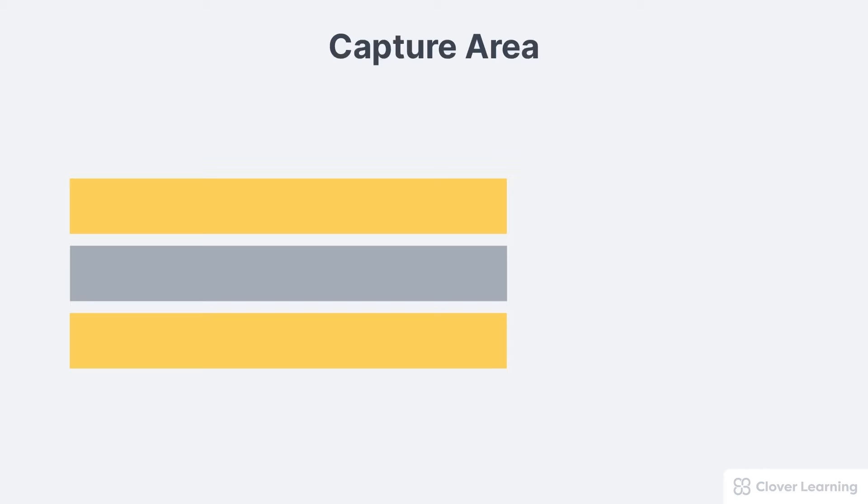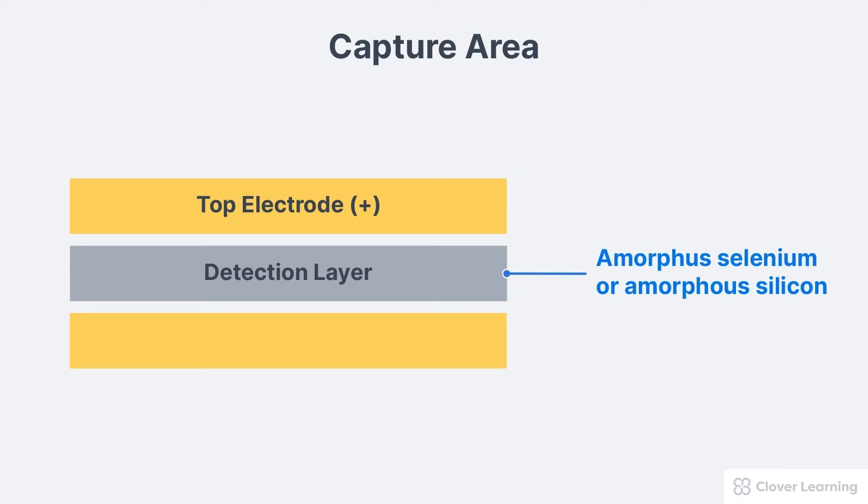The capture area has three layers: the top electrode, a sensitive detection layer composed of either amorphous selenium or amorphous silicon, and a bottom electrode.